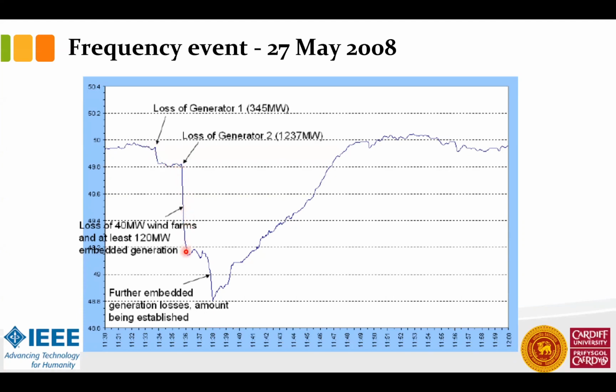Now what happened was, with that frequency drop, these small wind farms have under-frequency relays. They start operating and removing the wind farm, so they removed around 40 megawatts of wind and 120 megawatts of other small generators. Loss of that is reducing the frequency even more.